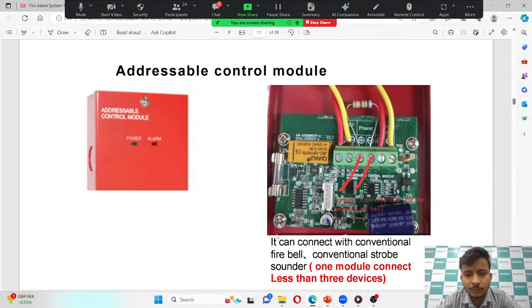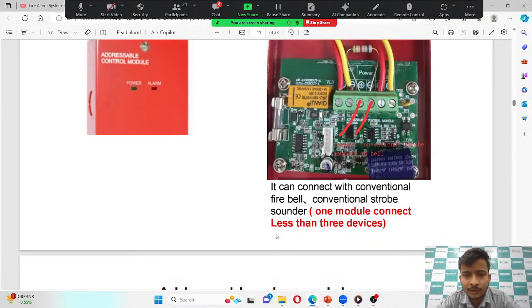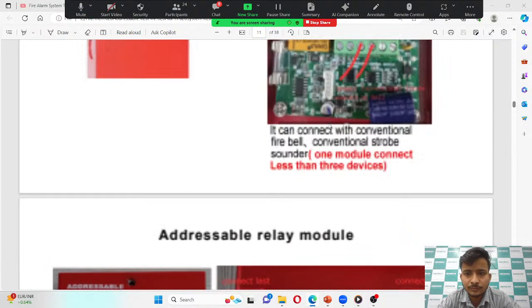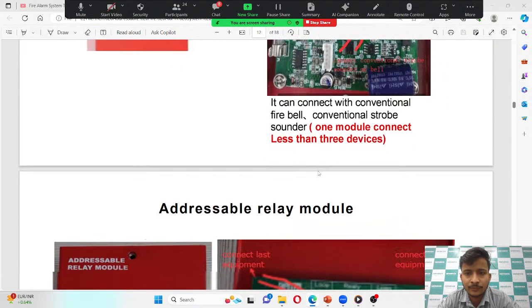Then the addressable control module, same as the monitor module, you can connect a conventional bell and sounder strobe with the help of this module. With one module you can connect less than 3 devices, which means you can connect up to 2 devices maximum with one module.